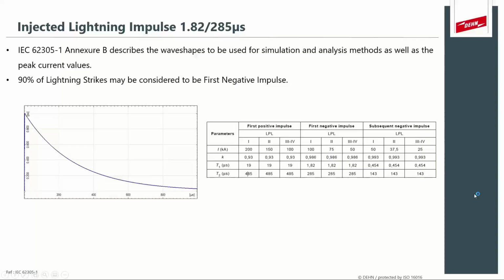But for first negative impulse, which we'll use now, we will be using 1,82 by 285 for this webinar, for this example. Because lightning protection level 3 and 4 is the most common all over the world, we will use 50 kA in the first negative impulse. That will cover most of the situations that you'll see all over the world. If we enter these values into the XGSLab time domain, or XGSLab TD, module of the software, it gives you a lot of flexibility to adjust the wave shape exactly the way you want to. You enter the values the same way it's read off from the standard: an adjustment factor, K factor, and then the rise time and the fall time, T1 and T2, 1,82 by 285. The 50 kA is injected in the same manner you would have injected a fault current within the system.